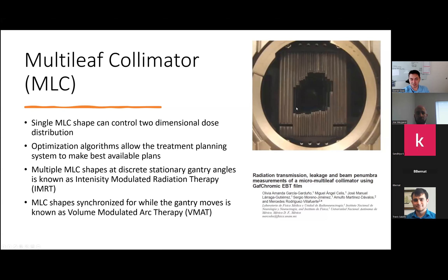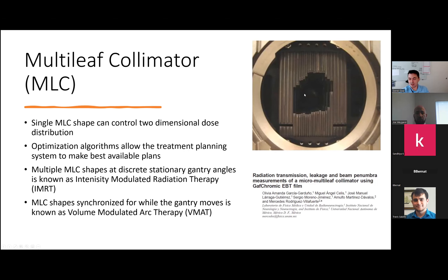Introducing the MLC and IMRT — if anyone has tried forward planning, the more segments you put in, the longer it takes a human to plan. So at the onset of the MLC, optimization algorithms were introduced, which allow the treatment plan to figure out the best segments and best monitor units to hit your target and spare your OARs or critical structures. Once you synchronize the MLC with your gantry positioning, you can get into the very fancy technique of volume modulated arc therapy.